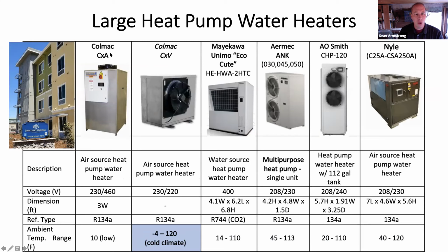Using a Colmac, a large air source heat pump, it takes heat out of the air and puts it into the recirc loop. This isn't a particularly efficient recirc system. If you're doing this as a boiler replacement in Michigan, like a big gas flame under a big old tank recirculating heat through a building, you'd probably start with a Colmac CXV because it goes down to -4 Fahrenheit, and you could take it up to about 120 Fahrenheit, which isn't quite hot enough.